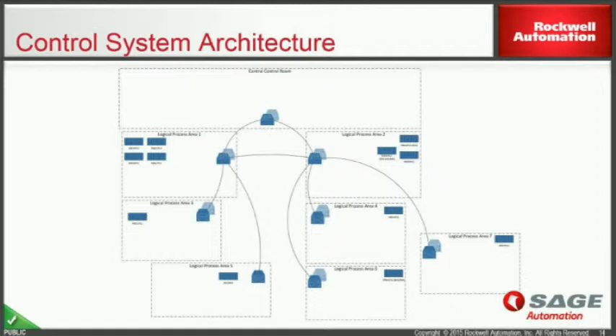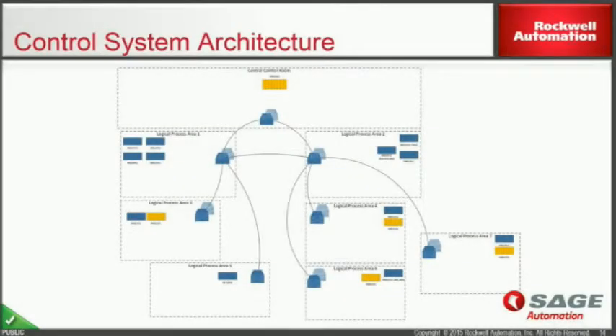We had a number of installed controllers, a combination of 12 redundant and non-redundant PlantPAx controllers, ControlLogix controllers, across the 7 process areas. 5 advanced controllers, 1 in the central control room, providing remote activation of critical functions like emergency stops, drown functions, things like that, and 4 in particularly hazardous process areas. And they were also talking to each other. They were talking to their local ControlLogix controllers via CIP comms, and they're also talking to each other via safety communications, all on the same network.